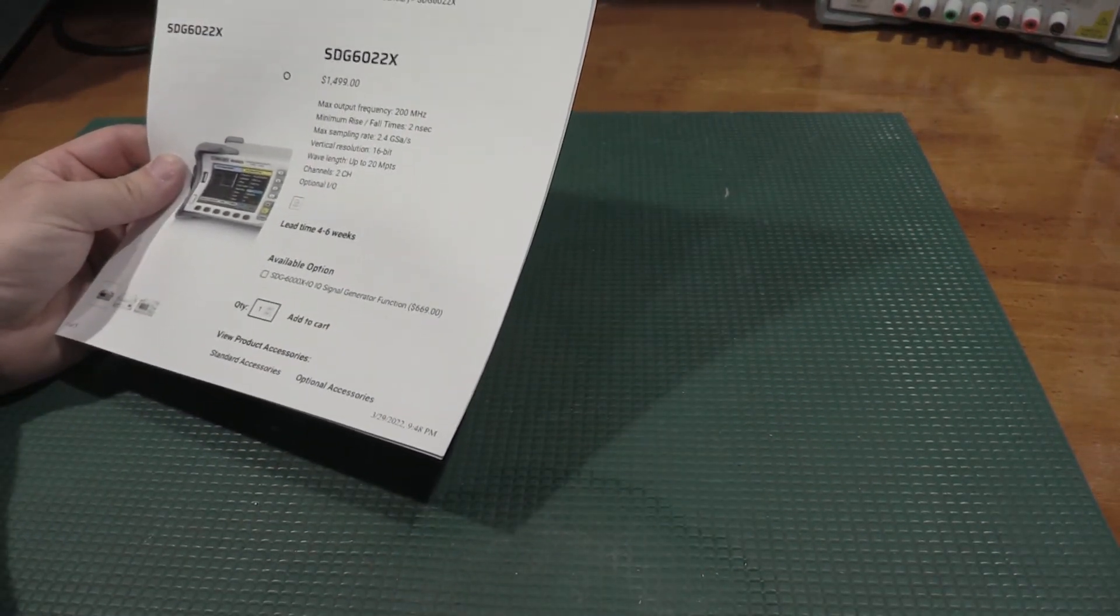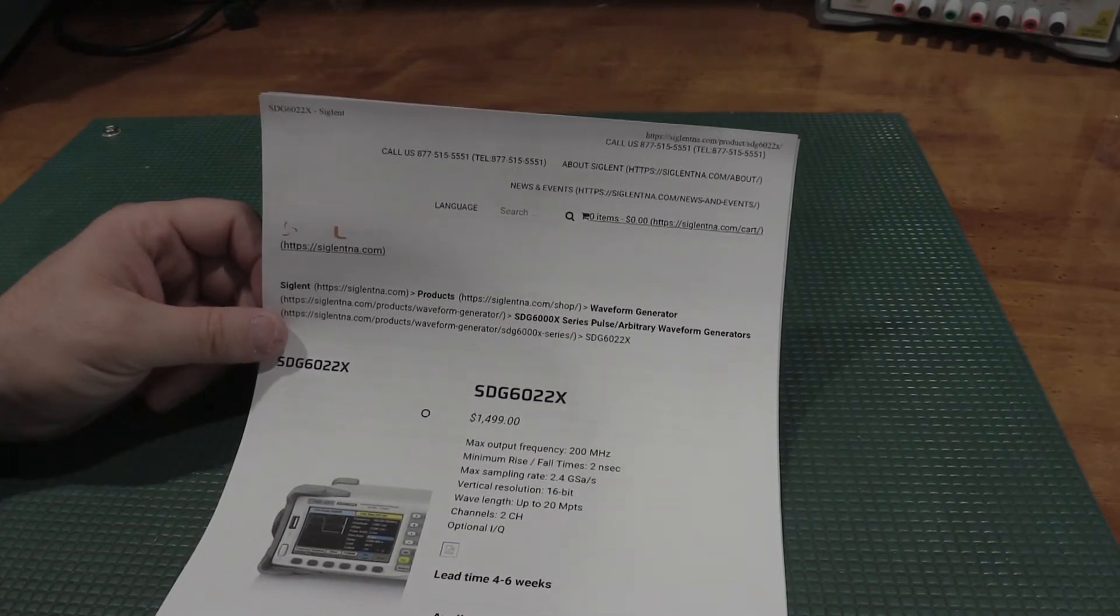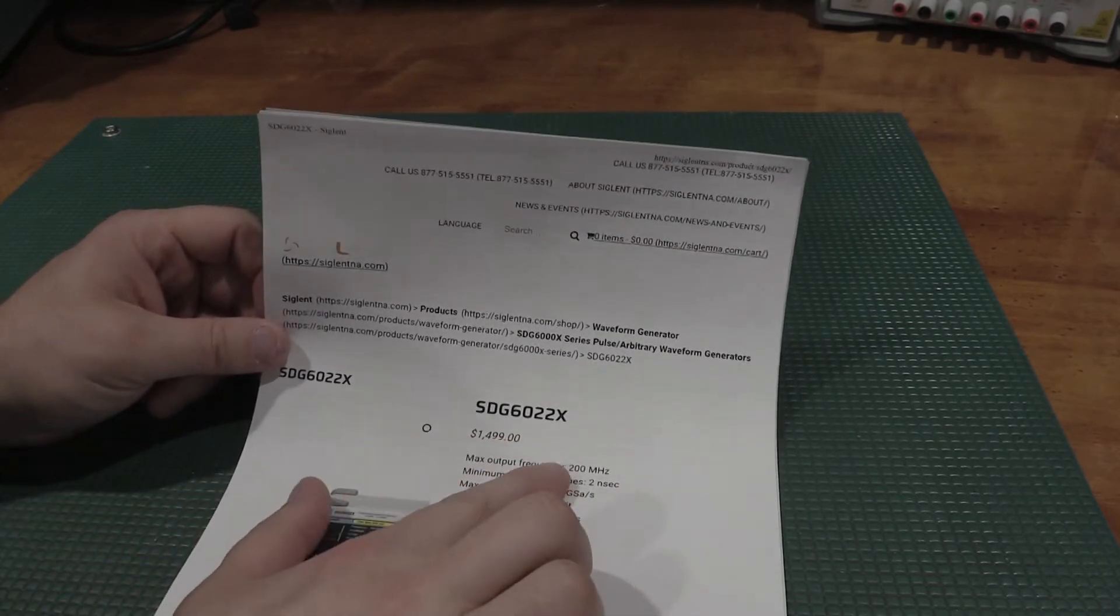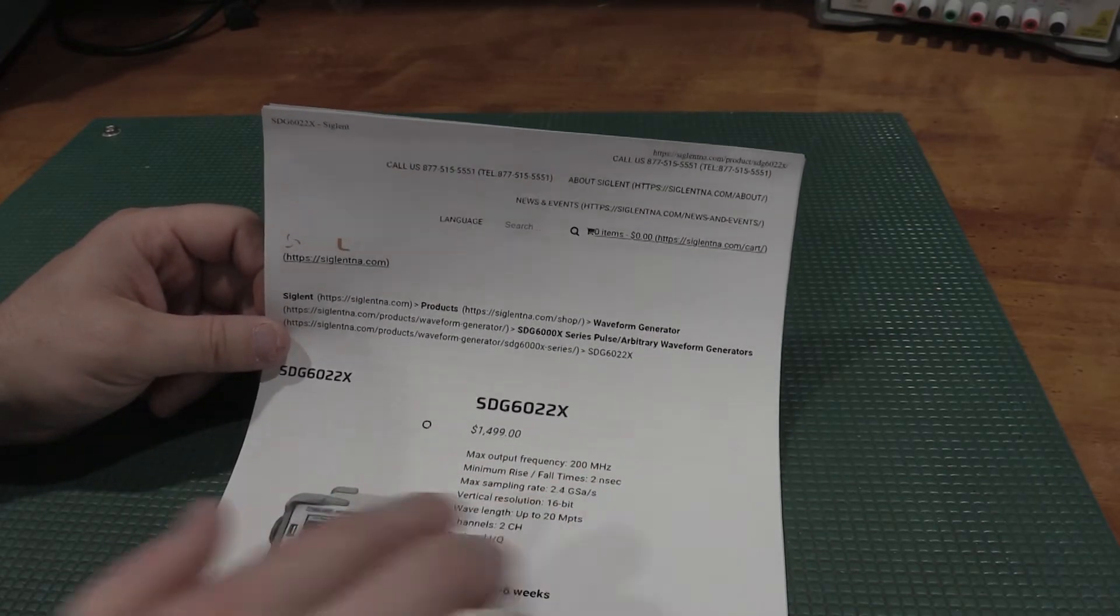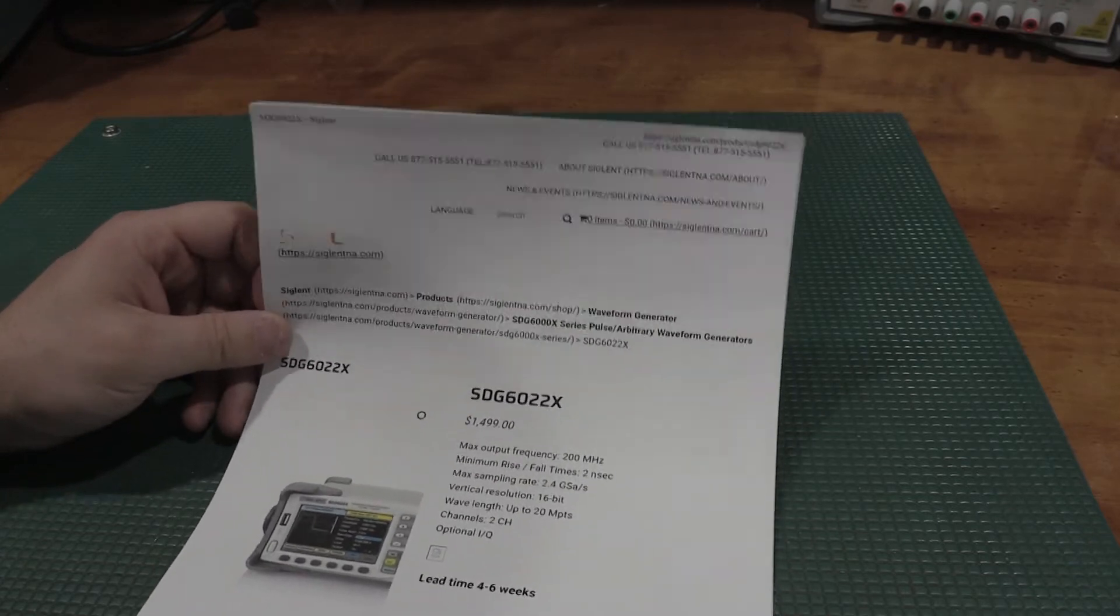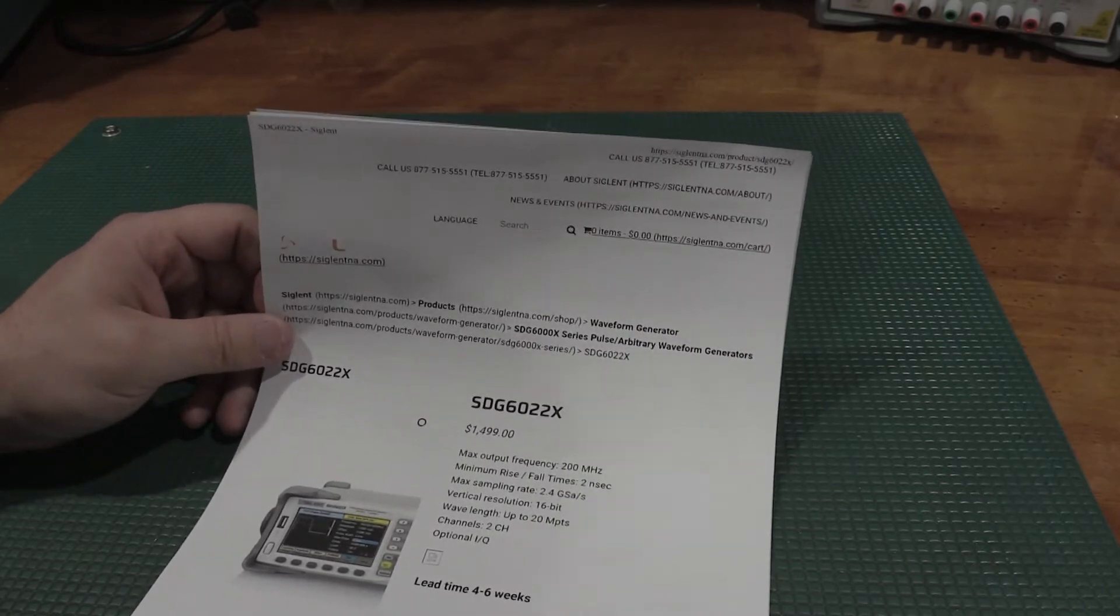Okay. Gear acquisition for the lab. This is what I'm currently thinking. I'm getting a lot of questions about can you use a function generator to calibrate a scope? Because a lot of people don't have some of the same gear that I have here in the lab to do the scope cals. So I'm thinking this is where I want to hit. It's a Siglent function generator. The important spec on this is not necessarily the maximum frequency, it's the maximum rise and fall time of 2 nanoseconds.